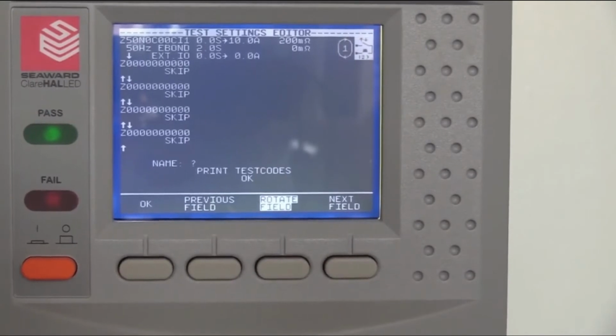And finally, for this test, we just want to define how we want to start the test. Now, there are a number of methods we can use to start the test. We have the green button, we have the guard switch, or we have a combination of both. Alternatively, you can set the test to none. So in essence, the test would perform automatically without any interaction from any person.